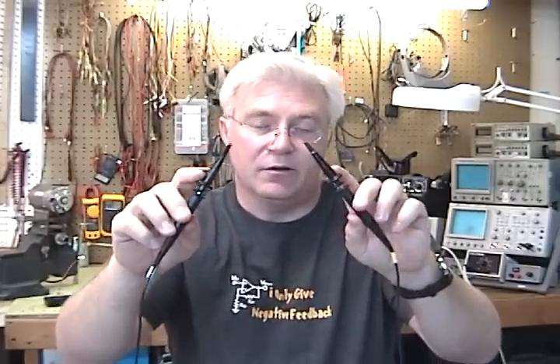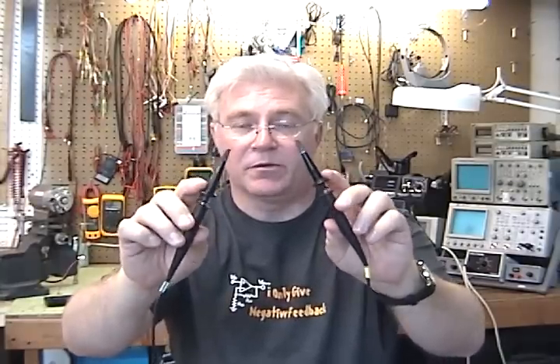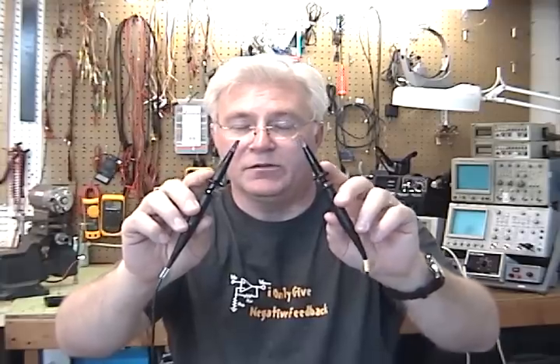But with a two probe system, without an isolation transformer, you can hook up this probe to any point on your circuit and this one to any point on your circuit. They're both high impedance probes, 1 meg to 10 meg depending on the probe you've got. Then you set your oscilloscope to see this waveform referencing ground mains, and this probe referencing ground as well through the chassis. Then you tell your scope, in a math function, to subtract these two voltages and show the new waveform. That'll tell you not only the shape of that subtracted waveform, but its values.